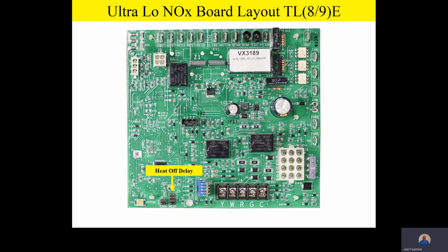Now, typically, we will ship it from the factory on C. Now, please write this down. A is 60 seconds, B is 90 seconds, C is 120 seconds, and D is 180 seconds. So this is very, very typical. I think we have one model of a furnace that maybe has a little different timing, but a very, very typical timing will be 60, 90, 120, and 180 second heating off delay.